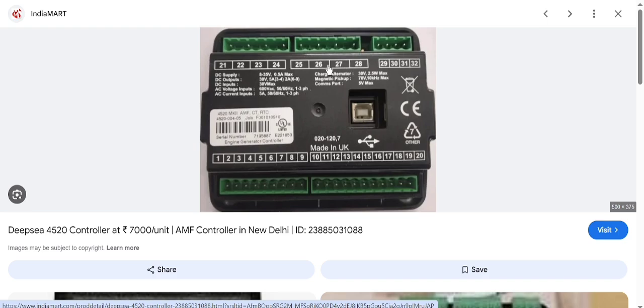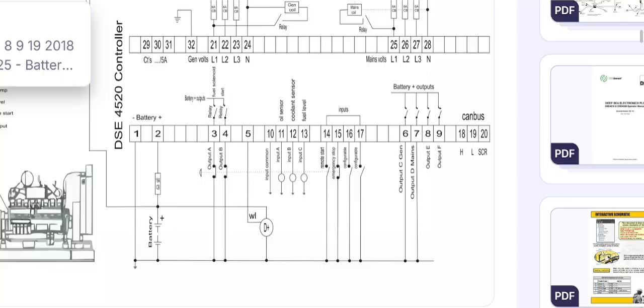This is the main input, this is the genset input, the current transformer input, and this is the gen input, and this is the main input. And here we have some sensor inputs and an emergency push button input, as you can see here. So let me go back and explain this completely in the block diagram of this controller, especially how to operate this auto mains failure controller. So let's go back and open the wiring diagram.